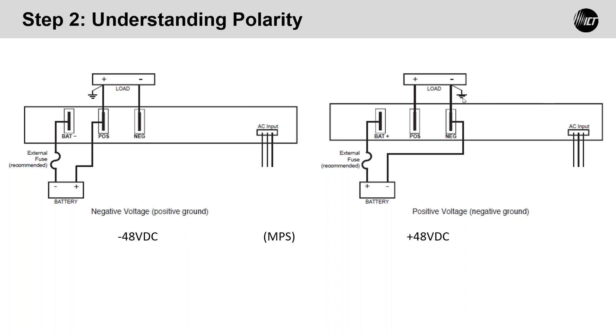If we have a plus 48 system, then the opposite is true: the plus side of the battery is carrying the load. We've got a fuse between the battery and the rectifier. The rectifier is BAT plus, and the minus side is the return. So in this case, it's just the opposite — the energy, the load, is going to the plus side of the device, and the negative side is the return, referenced to ground.